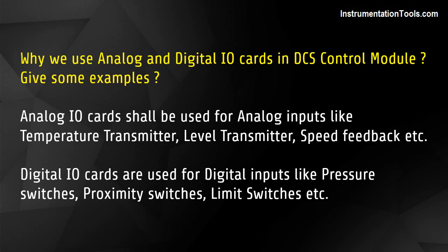Why do we use analog and digital I/O cards in a DCS control module? Analog I/O cards shall be used for analog inputs like temperature transmitter, level transmitter, speed feedback, etc. Digital I/O cards are used for digital inputs like pressure switches, proximity switches, and limit switches.